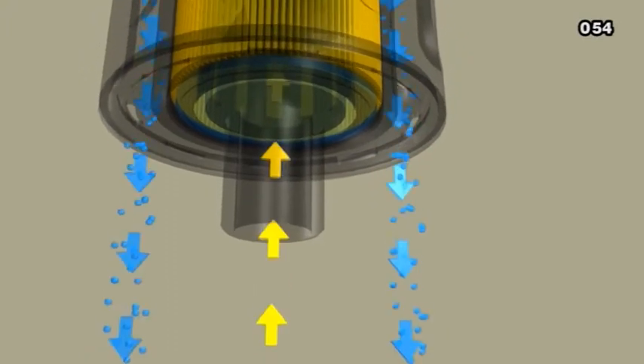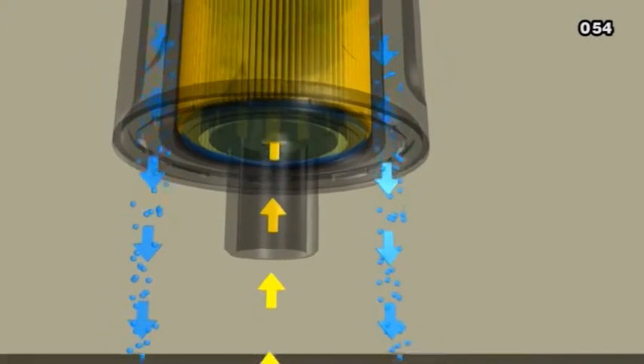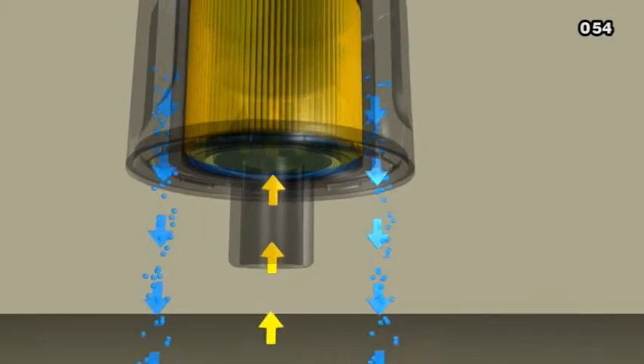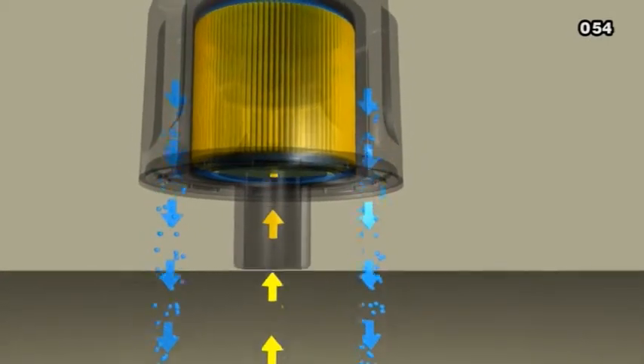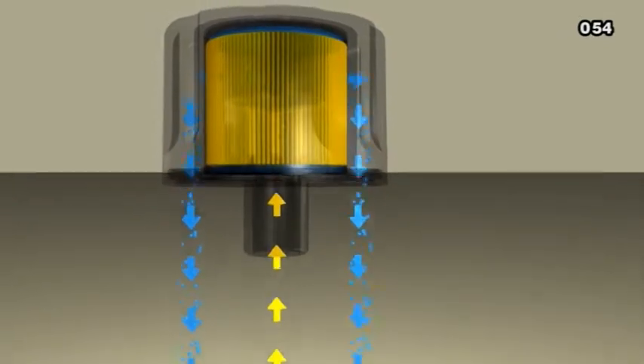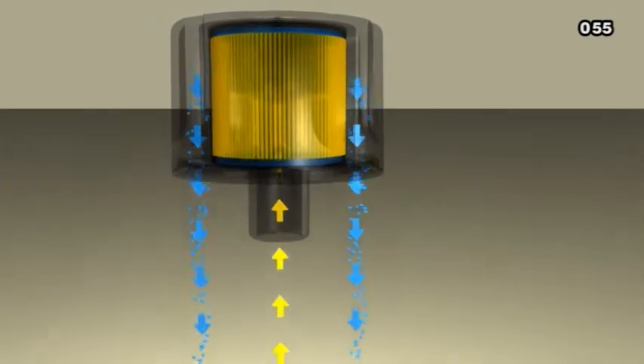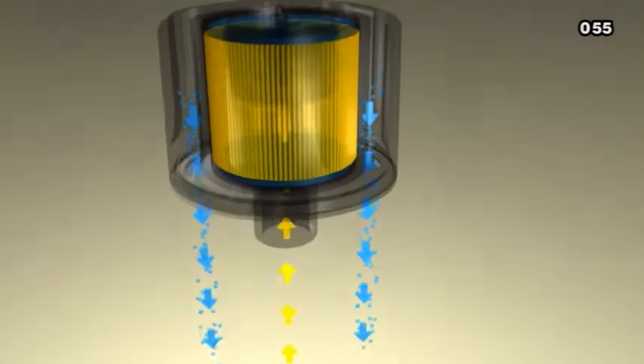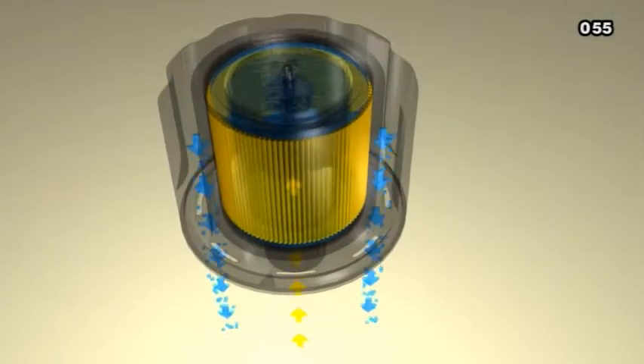When the tank exhales during the normal day-night temperature cycle, this exclusive, innovative Donaldson breather technology continuously regenerates breather water-holding capacity. This is in contrast to desiccant breathers that require frequent change-out.